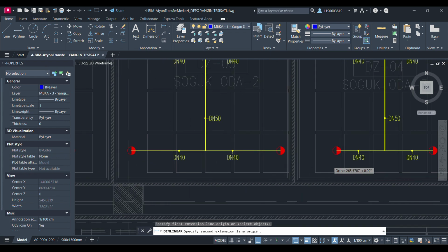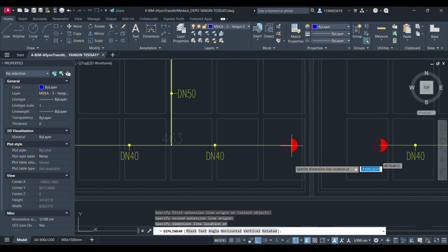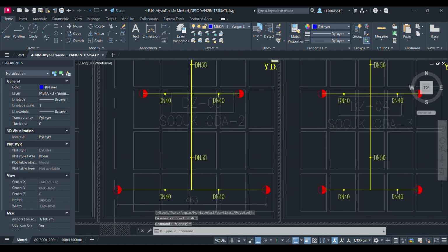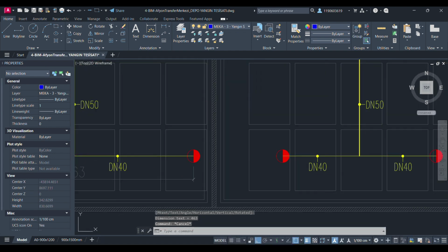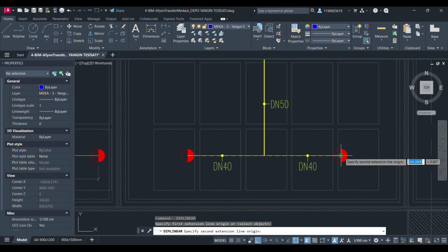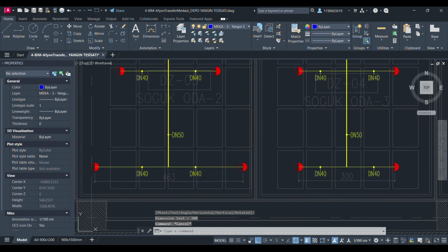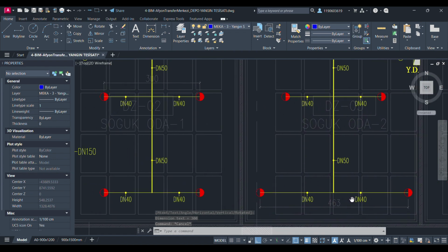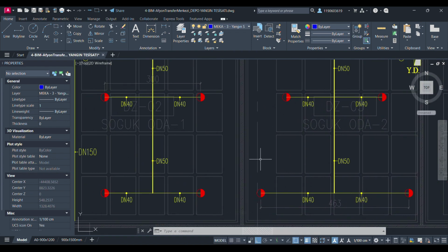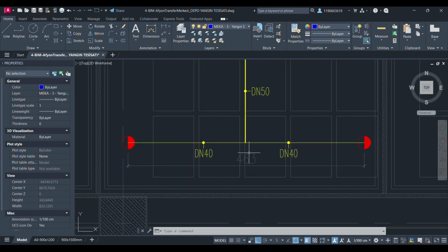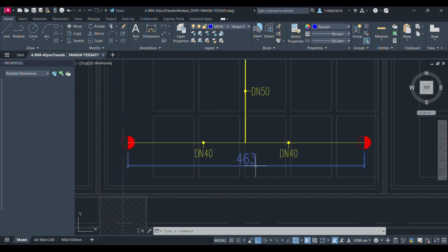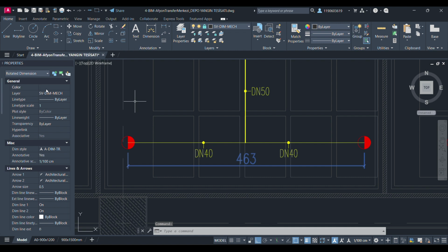How do we avoid this mistake? First, you must know the basic standards that define the distances between sprinklers in the execution plans. In regular rooms, the distance between sprinklers should not exceed 3.5 meters, according to international standards such as NFPA. In some special areas, such as warehouses or places with flammable materials, the distance should be smaller, for example, 2.5 meters. Don't forget about water pressure.